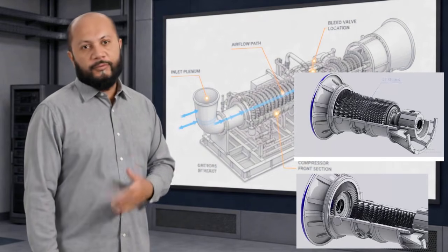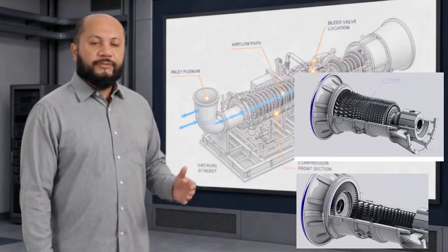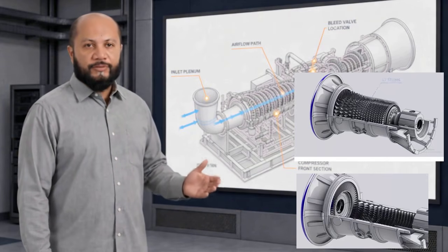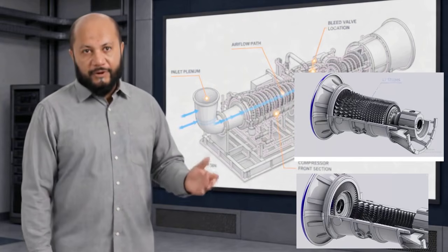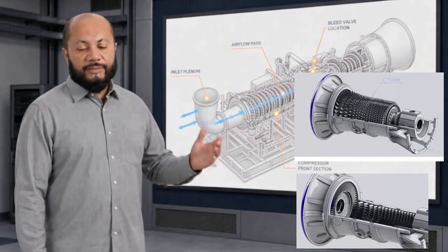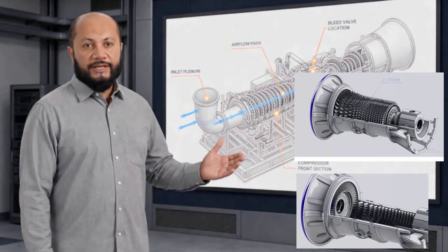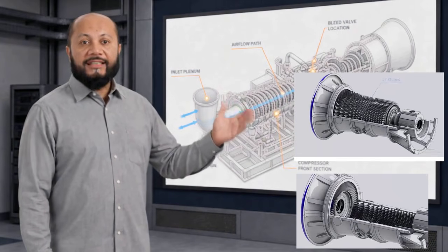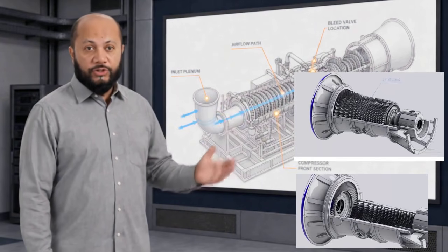17-stage axial flow compressor. During startup, the machine must be protected against compressor pulsation. The source describes the 11th stage extraction bleed valves as open during starting, while the variable inlet guide vanes are held in the closed position.